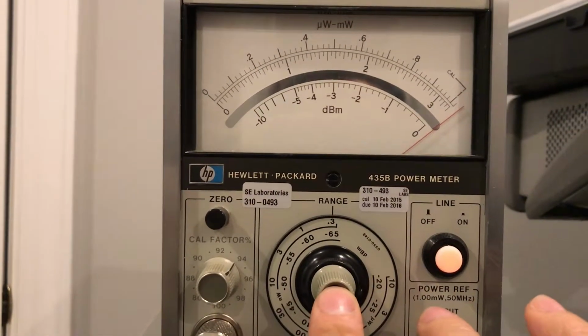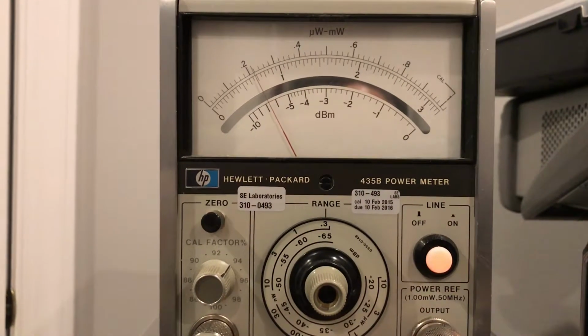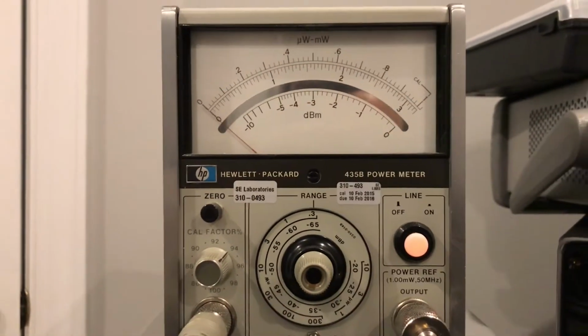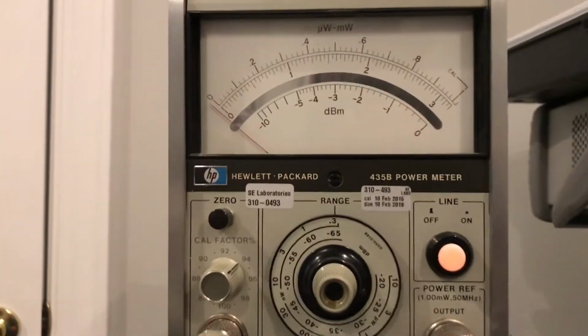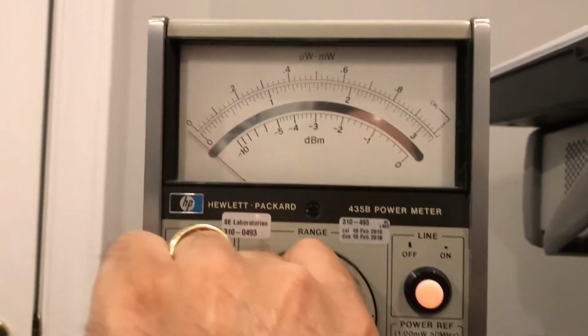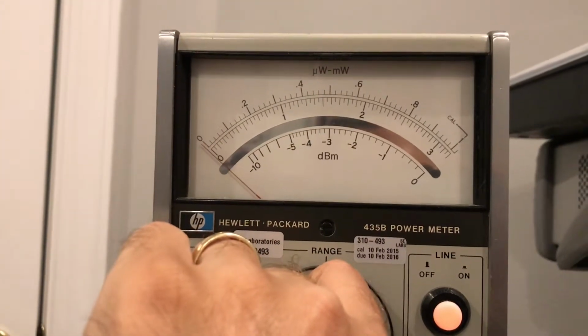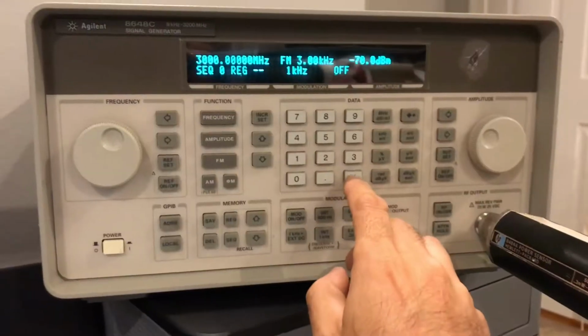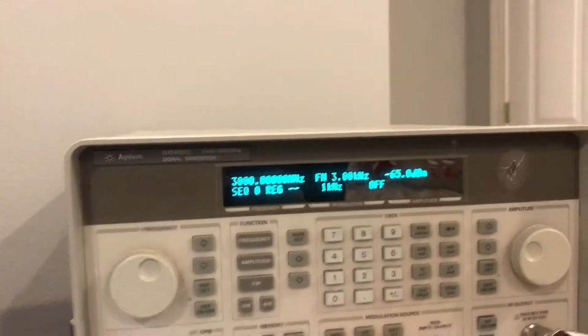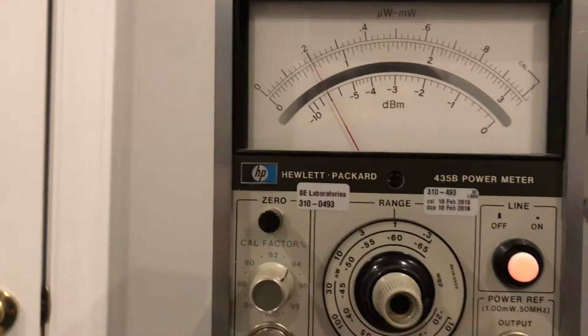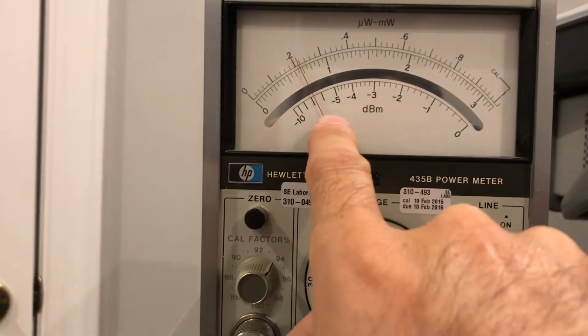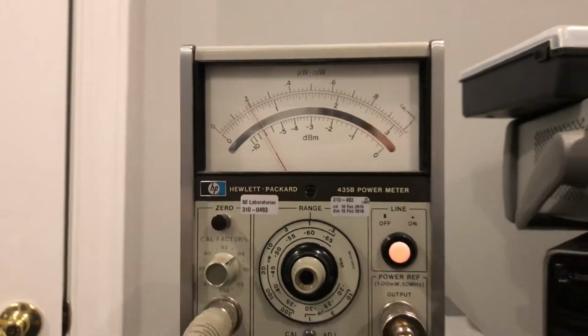I'll go ahead and take it to negative 70. So we're looking at now negative 70 dBm, and we'll see what the power meter shows us. So there you go. You can see there's a little bit of lag, and we'd have to let the sensor sit here for a little bit. But really, like I've said, negative 65 is really the bottom of the range that we're going to get. So again, looking at right at negative 67, just right at negative 67 dB.